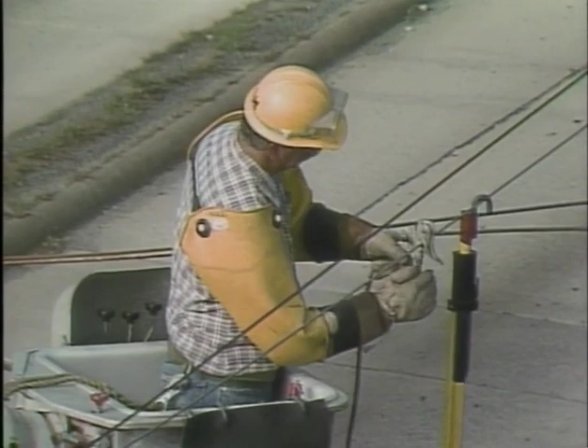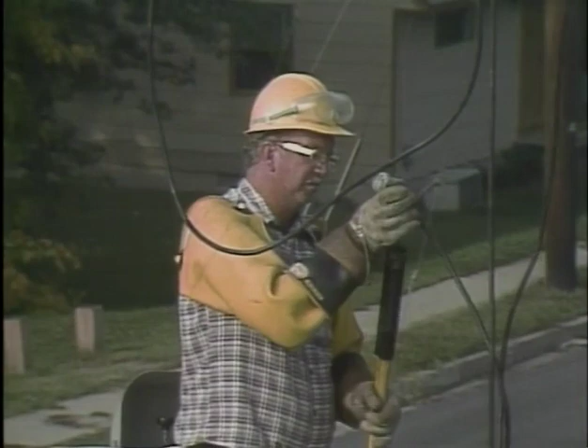In this example, one end of the jumper cable is attached to an established ground. The other end of the jumper is attached to the center conductor wire. Each of the other conductor wires is attached by jumpers to the center conductor wire. This creates one electrical path to ground for all 3 of the conductor wires. Now the worker can complete the maintenance on the lines safely.